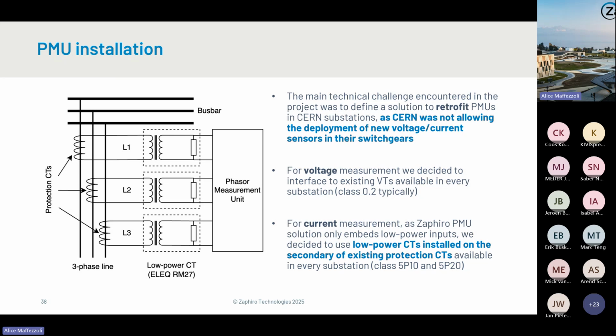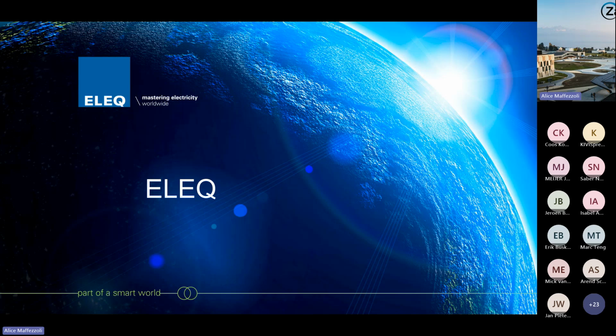Because we couldn't use our standard technology based on the Rogowski coil, we had to use low power CTs in series with the already existing CTs. So this is what we developed: there is a current CT that measures the current, and then on the secondary of this CT there is another CT in series that transforms the current waveform into a low power voltage waveform, which then goes into the PMU. ELEQ will explain more in depth, so I give the floor to Jérôme for that.